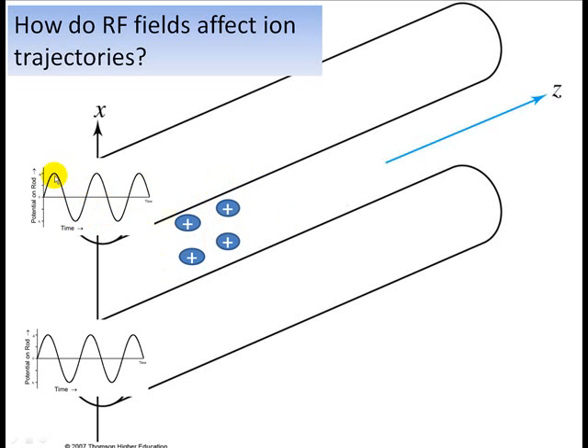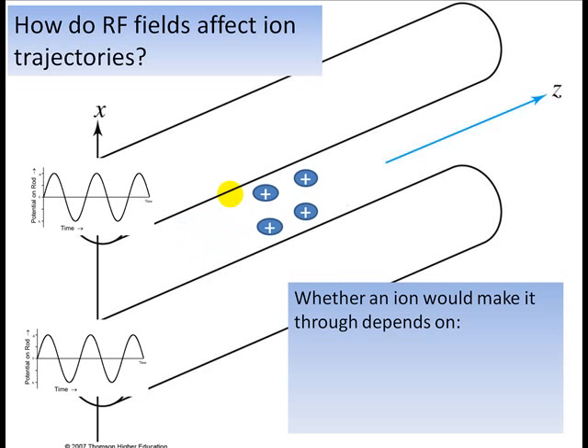So what happens to ions as they go down here with this voltage that's going back and forth? Actually, the times that the voltage is positive is not a necessary problem for the ions in terms of whether or not they make it through to the other end. They would just be repelled. But it would be a problem for the ions the times when these voltages are negative. And the ions would be attracted to the rods. And if they are able to actually accelerate enough that they are able to hit the rods, they're just going to crash there.